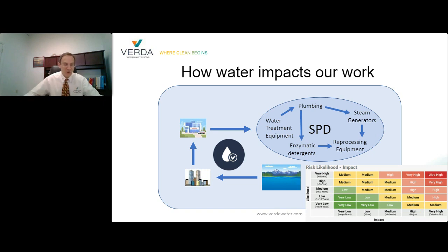First, the quality of incoming water can impact the performance of the water treatment equipment inside the hospital. If there's hardness in the water and it increases dramatically, your water softeners are now working harder, using more salt and needing more frequent regenerations. We've seen facilities where there's a significant drop in department water pressure during the facility's regeneration of their water softener equipment, or worse, the system bypasses softeners during regeneration and the SPD is fed very hard water during that cycle. The production of purified water for final rinsing is also impacted by the incoming water to the facility.